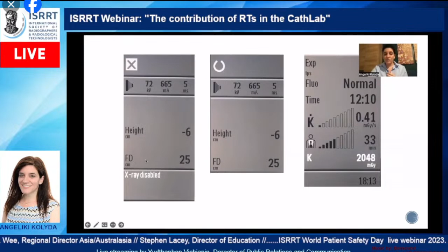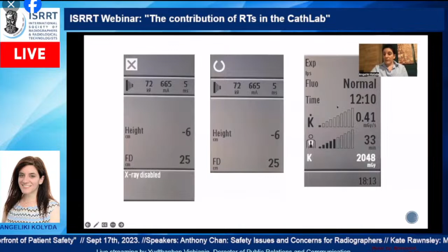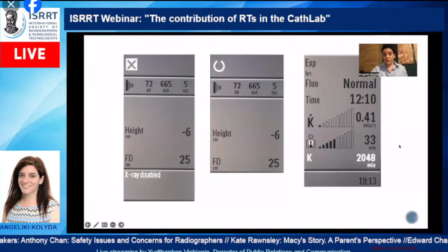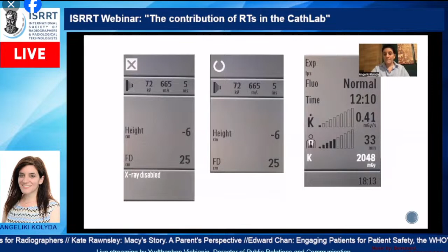Another thing that we can see is the frames per second. We prefer 15, and in some medical devices we have to choose 7.5 per second. Of course, we can choose the fluoroscopy mode. Here, for example, it is normal, but we can use low or high. It depends on the patient, the body mass. We can see, of course, the exposure time, and the air kerma. And we can talk with the interventional cardiologists and have a conversation during the whole procedure, so that if there is a lot of radiation exposure, we can stop the procedure if we don't have any result.